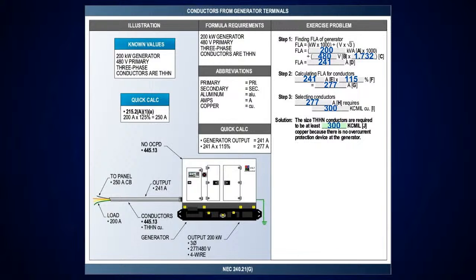And then I'm going to look at sizing these conductors. And the next size up above that is 300 kcmil conductors. Very simple. All of this is easy to follow. You just need to know where you're looking here. Okay. But the one thing I want to point out, when we were doing the secondary side of that transformer, the conductors for it, and then I'm doing it here for a generator, I still did the same calculation to determine what my full load amperage was. Okay. Right.